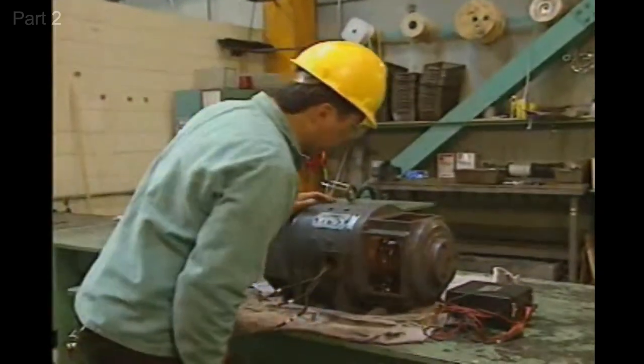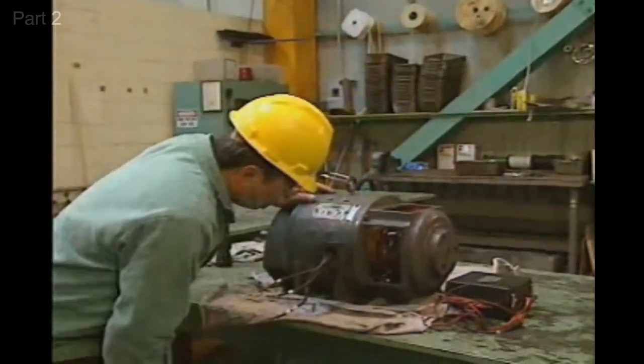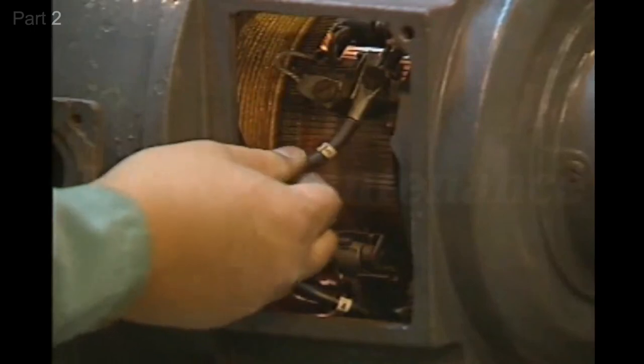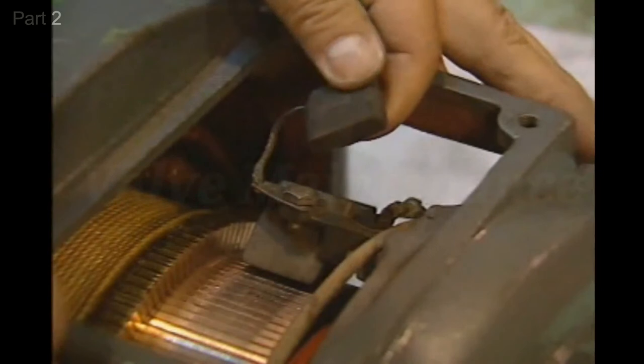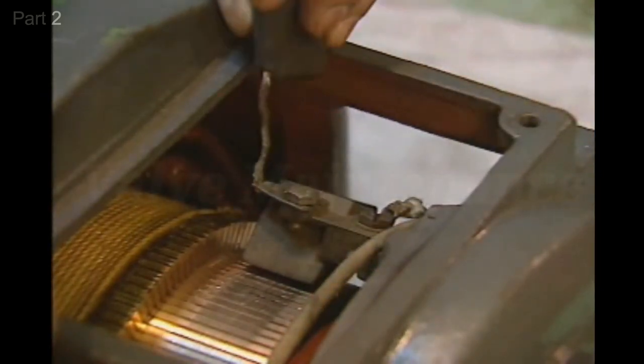First, it should be checked carefully for any obvious problems such as broken wires, loose screws, short brushes, and charred insulation. The brushes and the brush rigging should also be checked.